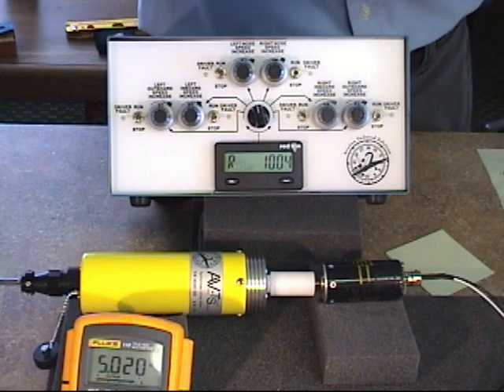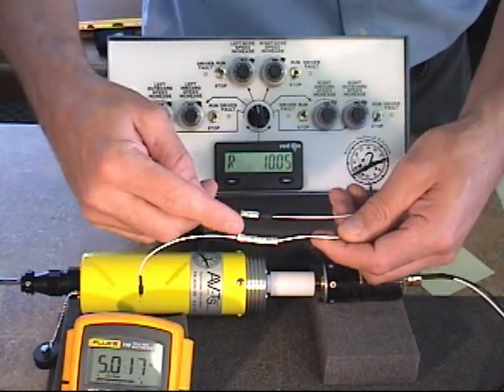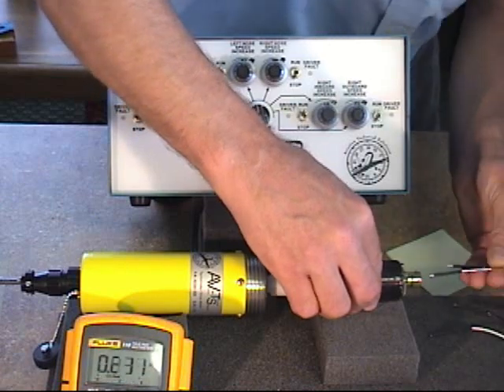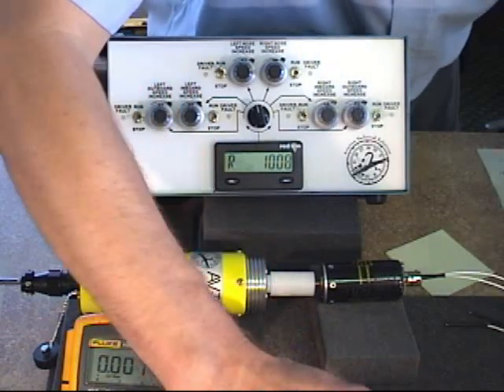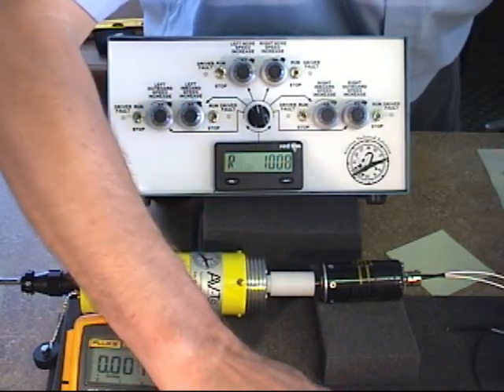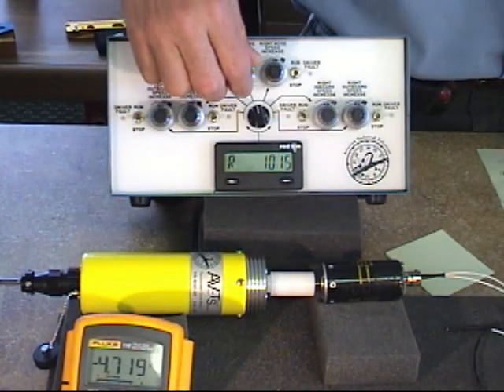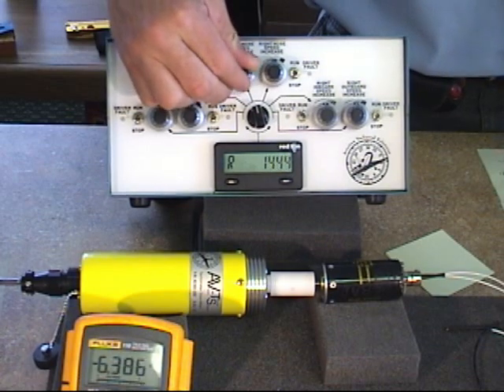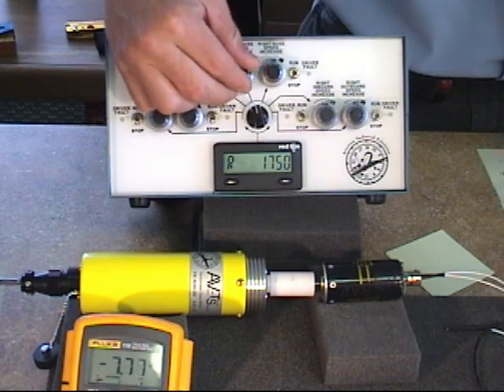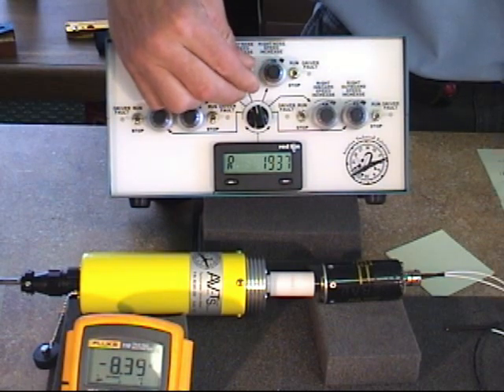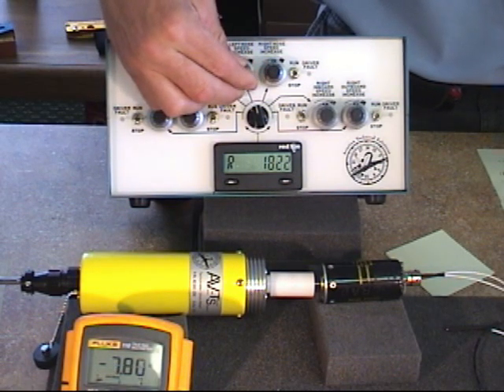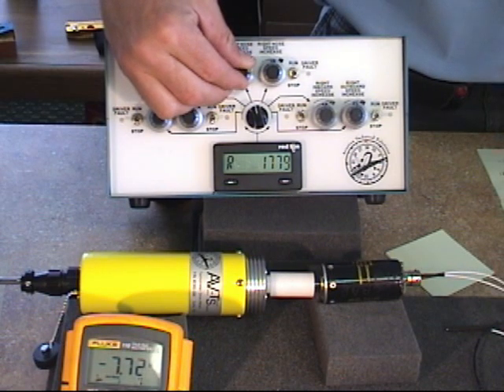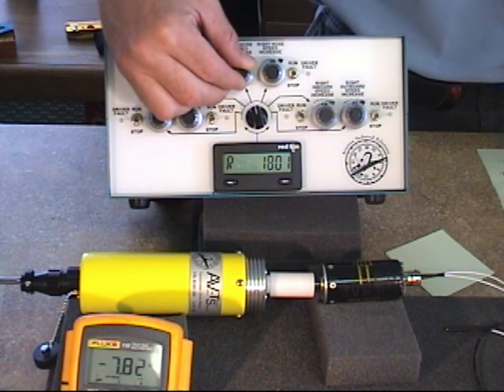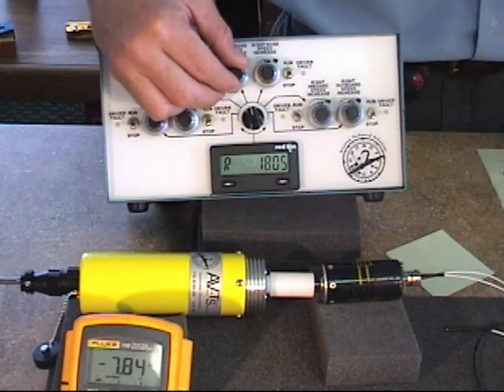We also have the ability, as per the CMM, to use a loaded lead. That's just a 5000 ohm resistor right across the leads. We can go right into A and C. And we can come right up to 1800 RPM here. And it looks like our output is 7.8 something. That puts us right in the middle of the range there.